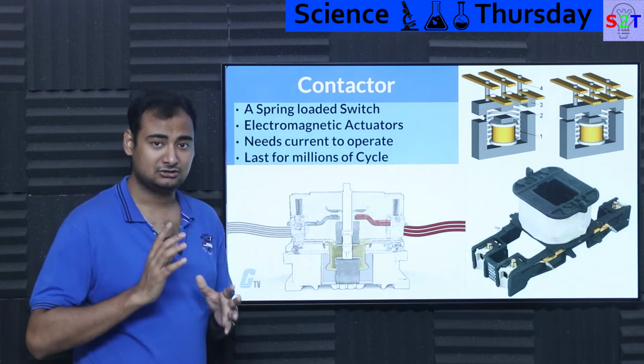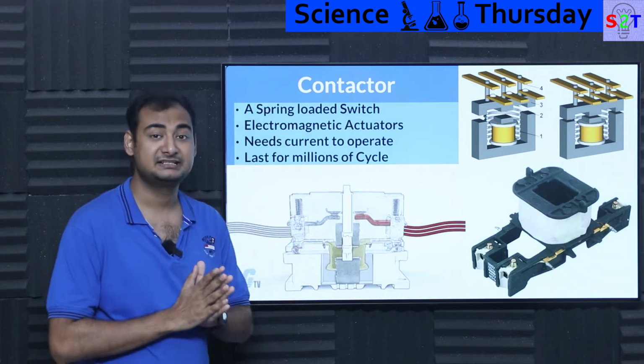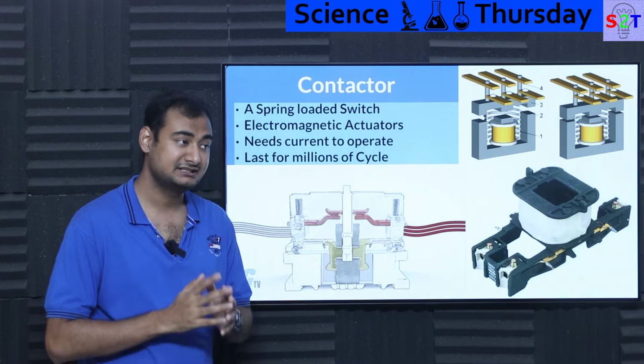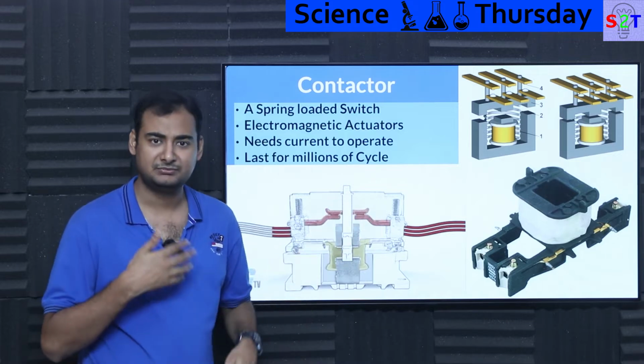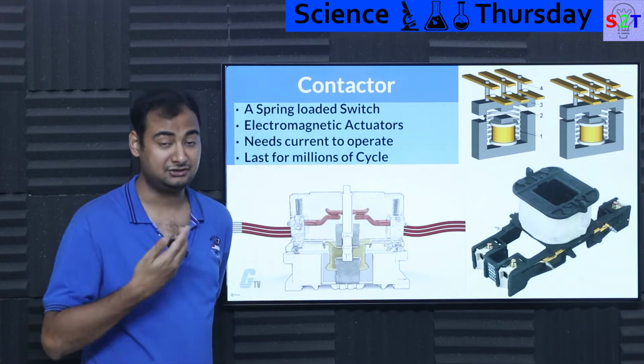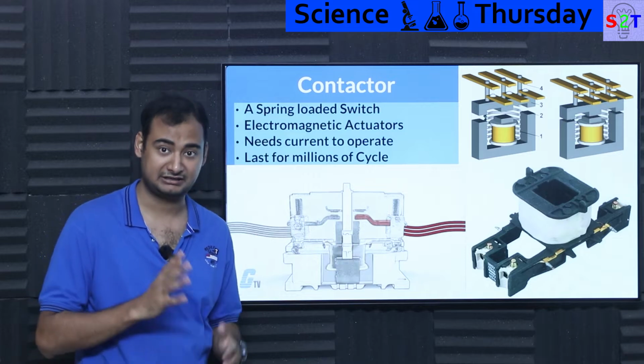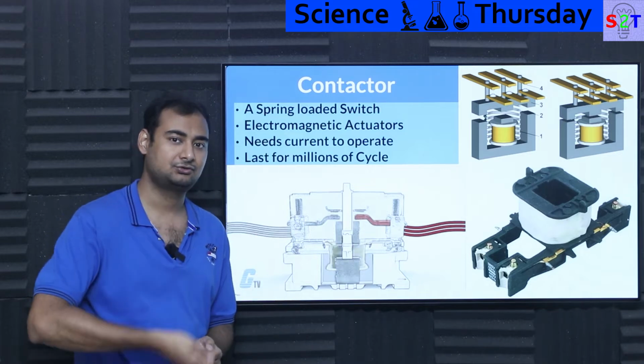Needs current to operate. Now the primary reason why we go for this is they can survive millions of cycles. What does that mean? That simply means if you have an MCB, you may think, hey, I have an MCB, it's designed to break a ludicrously large amount of inrush current and handle those sort of things. Why don't we just use that?